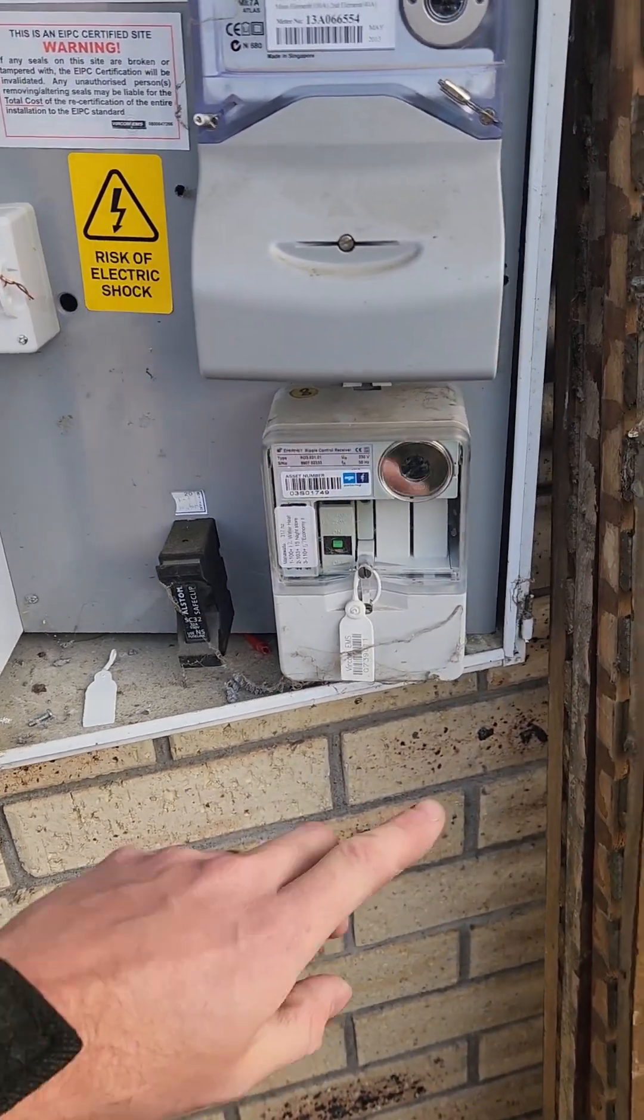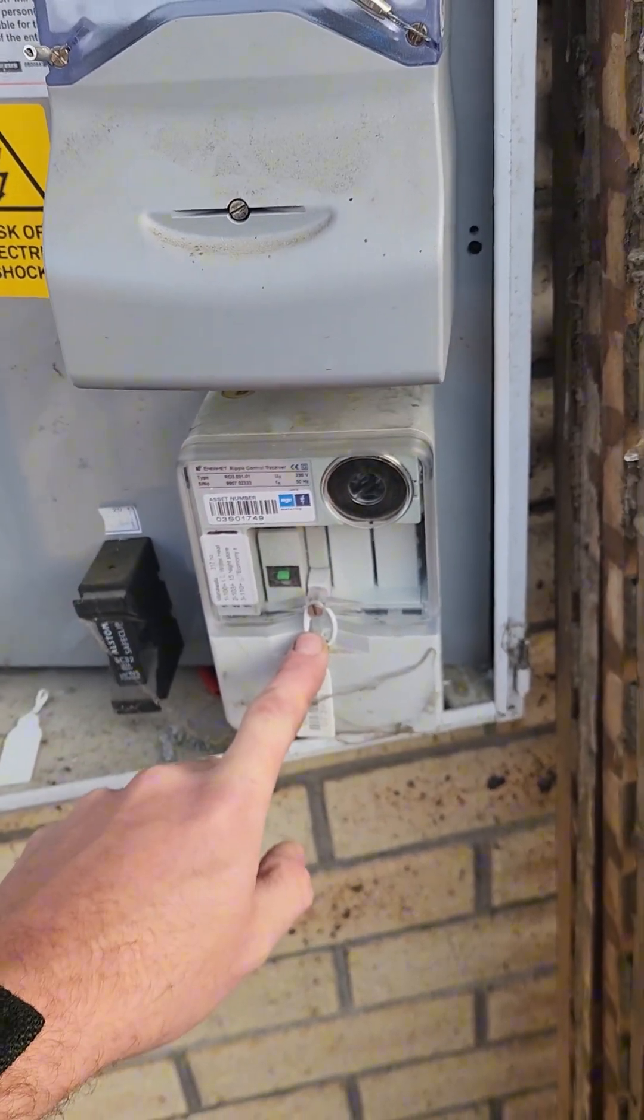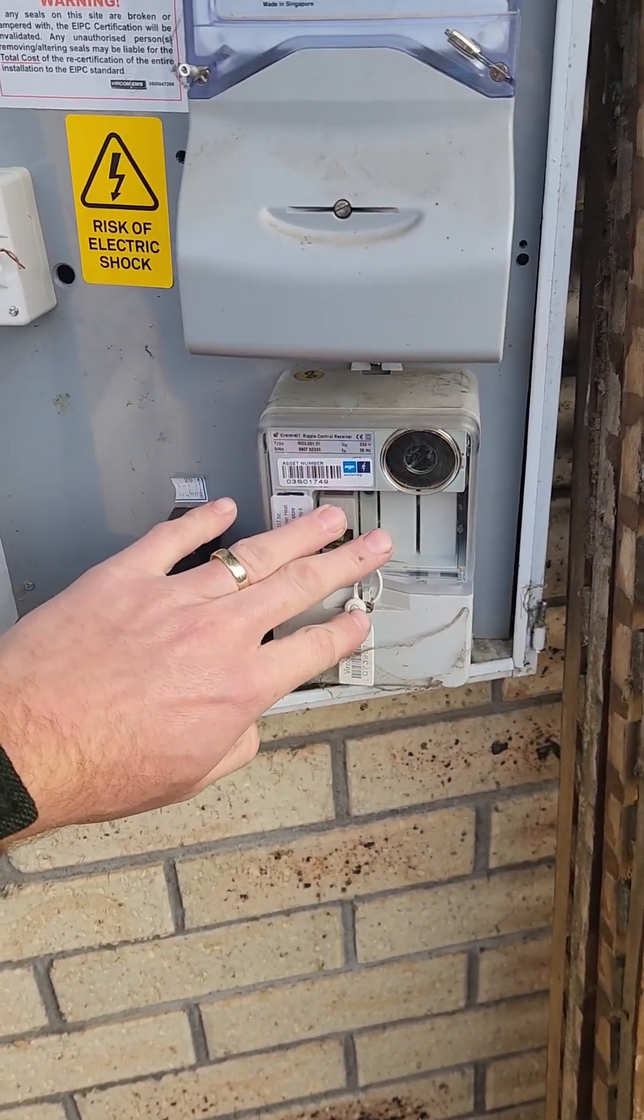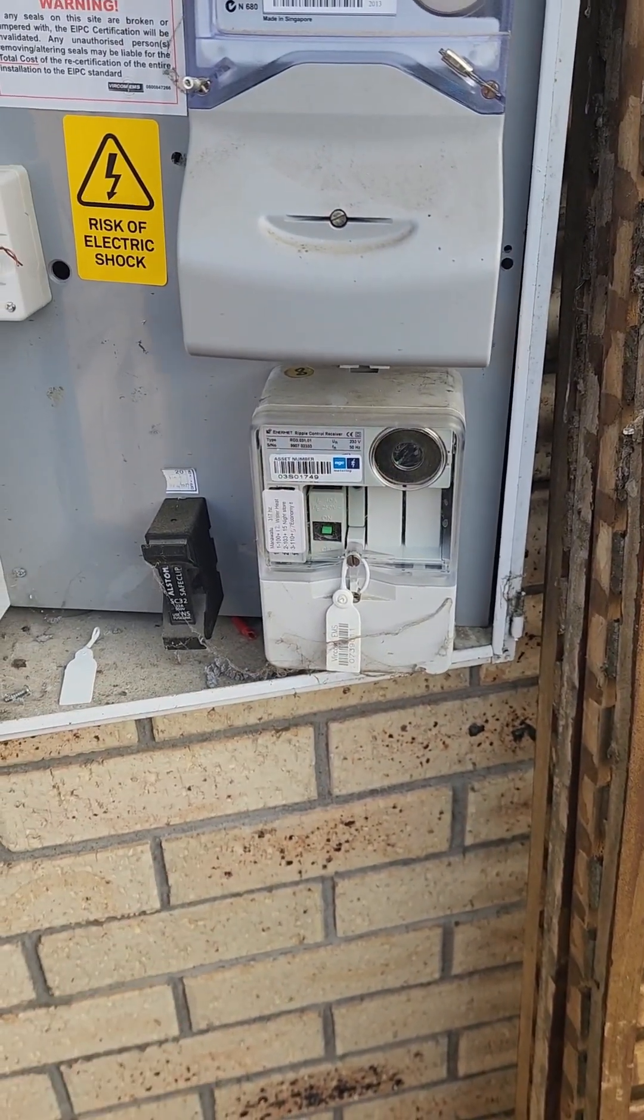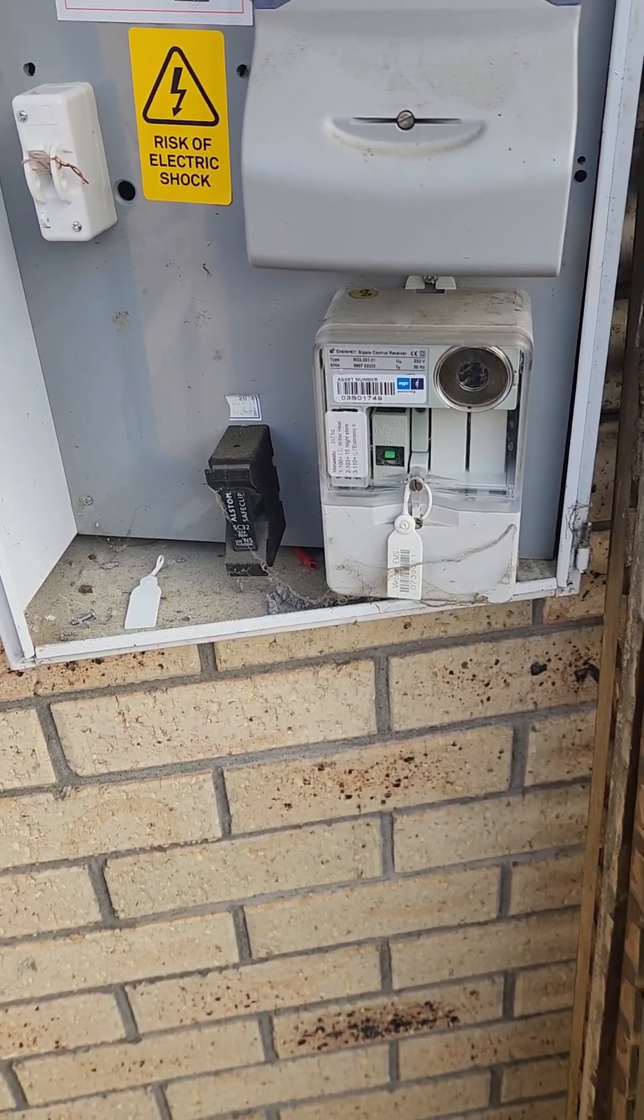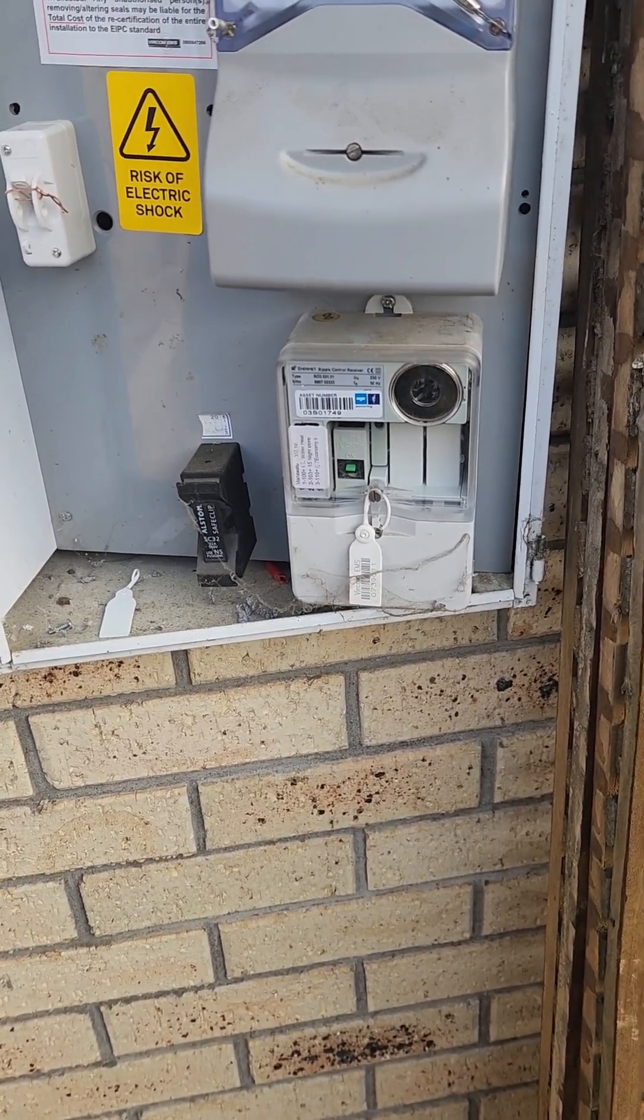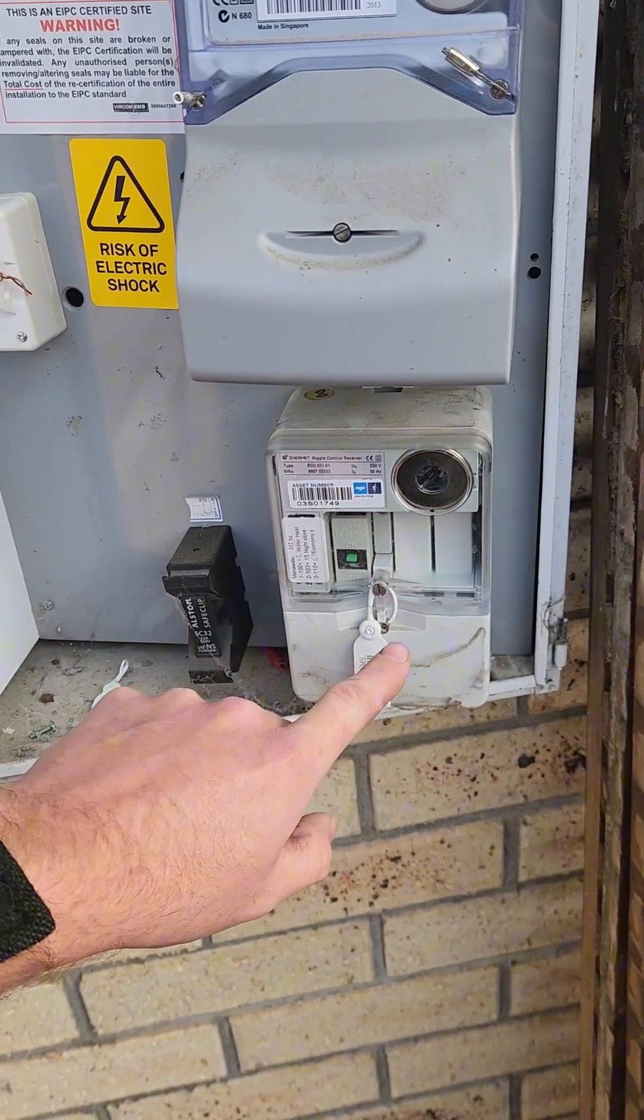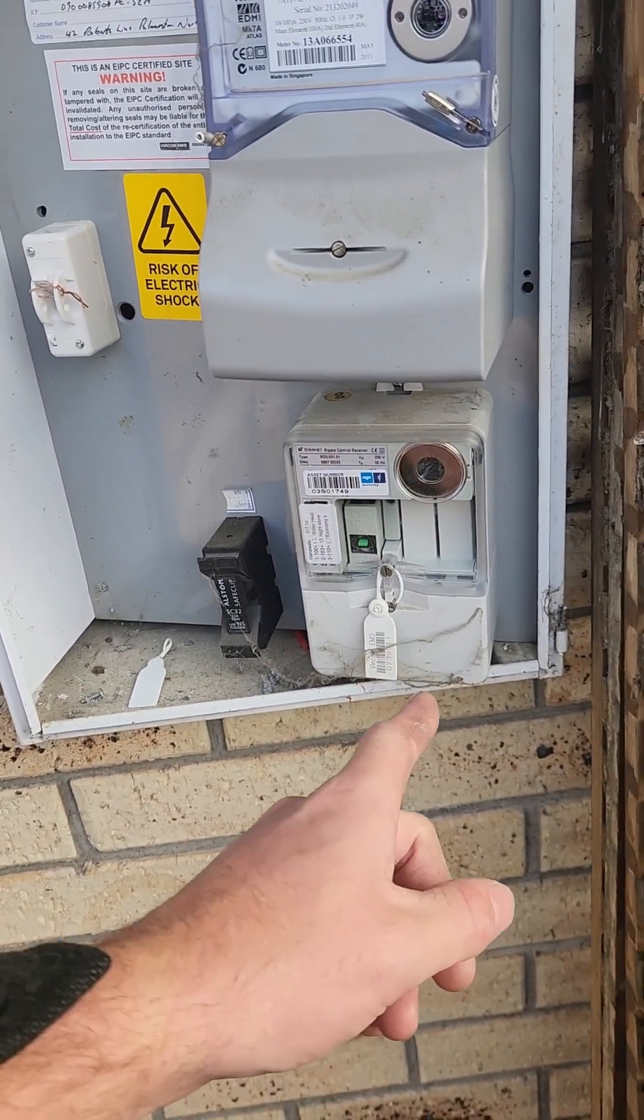This video is going to have a bit of information in it. This here is a ripple control so this controls your hot water and most houses will have them. We start to take them out when we put a hot water diverter in for solar but what this device does is it turns your hot water cylinder on and off and the power company controls that. The reason that they control it is when everybody gets home at night everybody turns all of their appliances on and it puts quite a lot of stress on the electrical grid. So they can use these ripple controls to turn off your hot water cylinder and when they turn the hot water cylinder off it just alleviates some of that stress on the system. So if you ever wondered what that's for that's what it does.